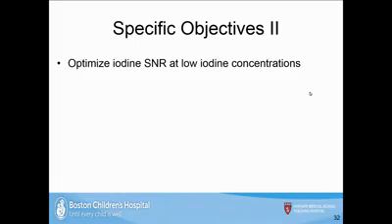A question was raised about whether the two DES images at different kVps have the same mAs and noise properties before subtraction. They typically don't have the same noise properties. Unlike CT where constant noise is important, for radiography it doesn't seem to be as big an issue. The mAs is actually one of the free parameters that can be tuned to optimize the noise in the output image — which is exactly what the next section addresses.